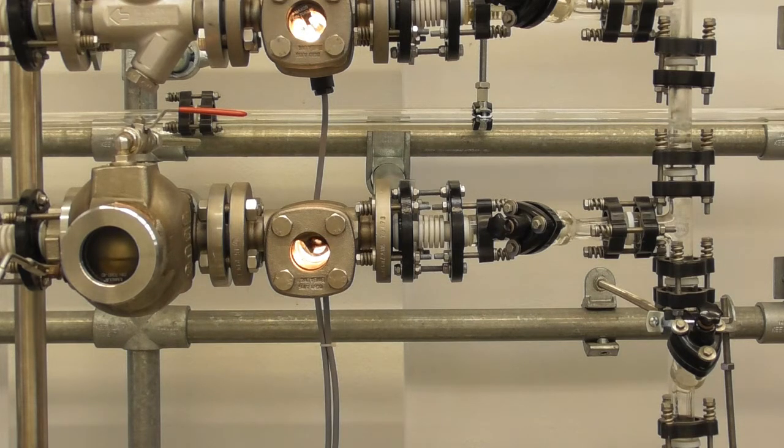By taking a look on the sight glass mounted at the steam trap body, we clearly see that the condensate level remains equal while the steam above the condensate cannot travel back towards the heat exchanger anymore. We got a steam lock.